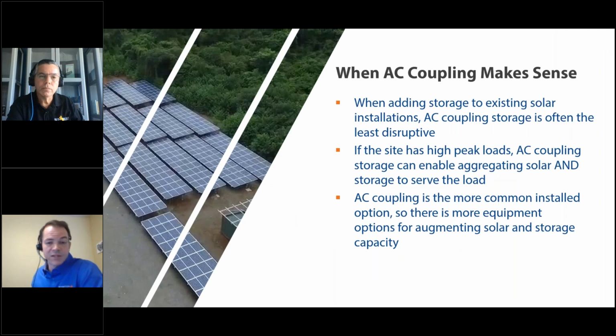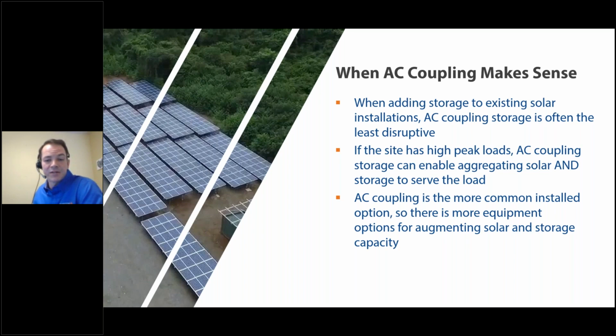So let's talk about when AC coupled systems make sense. A good example is if you're adding storage to an existing solar installation—AC coupling is often the least disruptive because you've already got a bunch of equipment on site, and you can add on an AC coupled solution. Another example is if a site has high peak loads on the AC bus, then adding an AC coupling system can enable further AC capabilities because you're aggregating the AC power of both the solar and the storage in order to service that higher load. And then the largest reason AC coupling is used is because it's the most common installed option, so there are more options of components and equipment out there, as well as more domain knowledge doing AC coupled solutions.